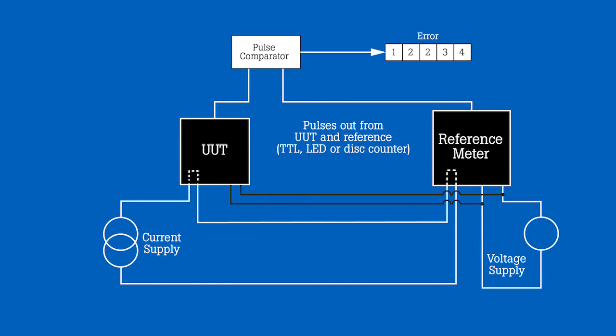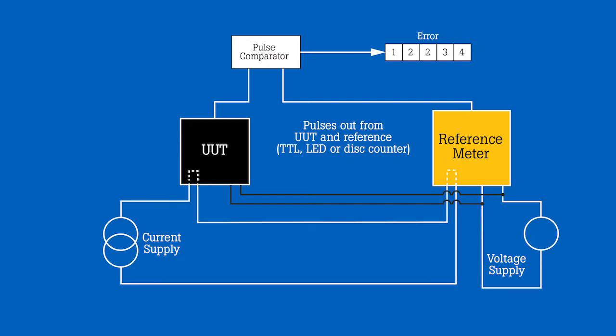Three separate pieces of calibration equipment are required to complete this task: one, a power supply that can provide three phases of voltage and current; two, a three-phase reference energy meter; and three, a device for counting pulses both from the reference meter and the UUT.